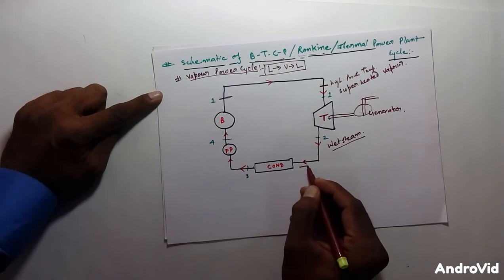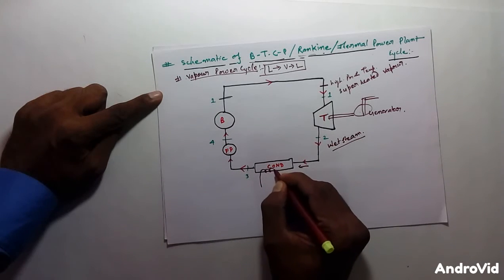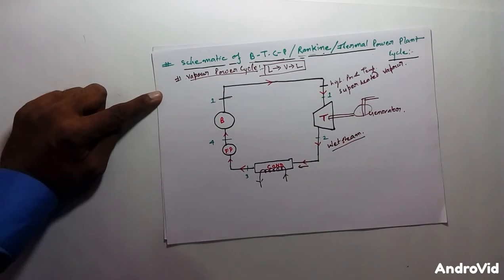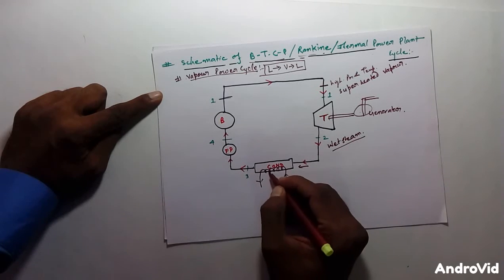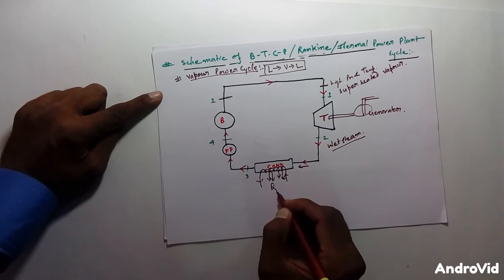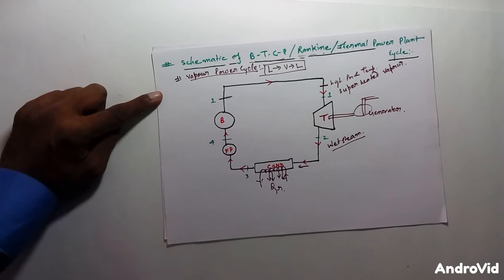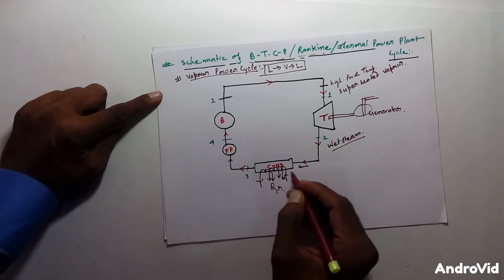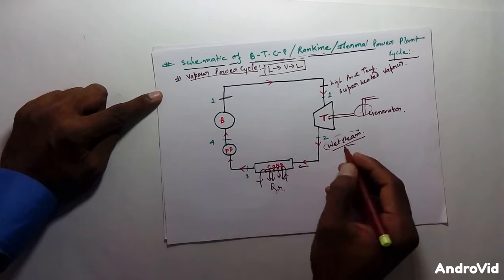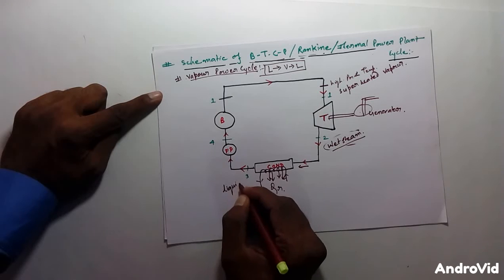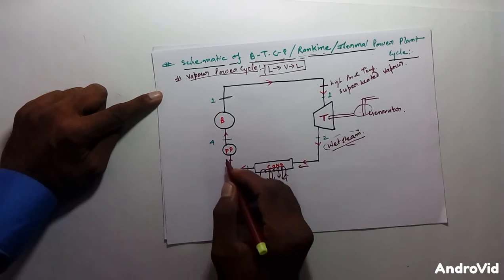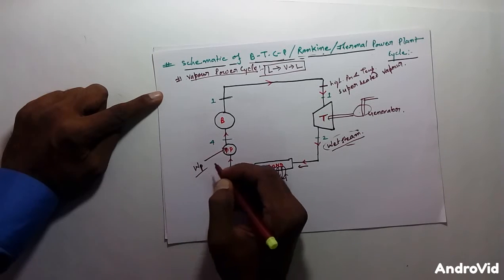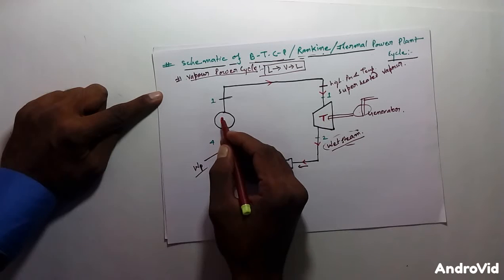When this wet steam goes to the condenser, the condenser is used to condense the wet steam into liquid. This is a heat rejection process — heat rejected QR takes place. After passing through the condenser, the wet steam transforms into sub-cooled liquid. This liquid is then sent to the feed pump, where we provide pump work WP to pump the liquid up to boiler pressure.